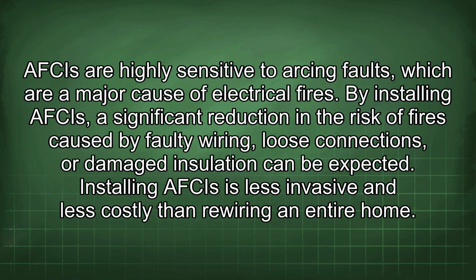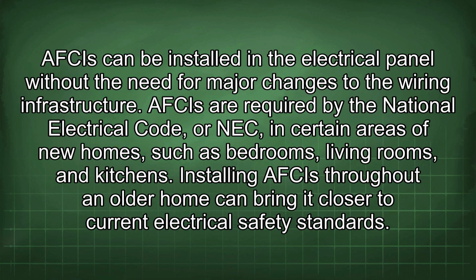By installing AFCIs, a significant reduction in the risk of fires caused by faulty wiring, loose connections, or damaged insulation can be expected. Installing AFCIs is less invasive and less costly than rewiring an entire home. AFCIs can be installed in the electrical panel without the need for major changes to the wiring infrastructure. AFCIs are required by the National Electrical Code, or NEC, in certain areas of new homes, such as bedrooms, living rooms, and kitchens. Installing AFCIs throughout an older home can bring it closer to current electrical safety standards.